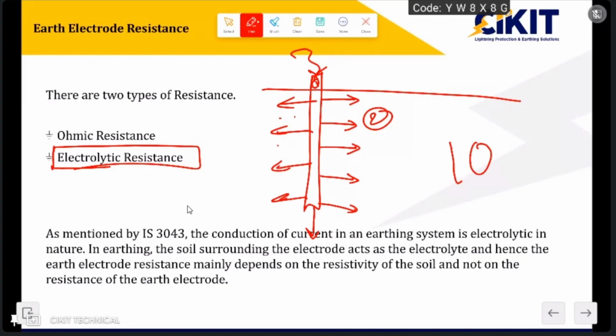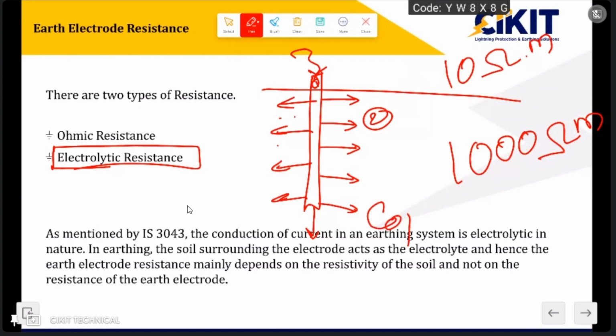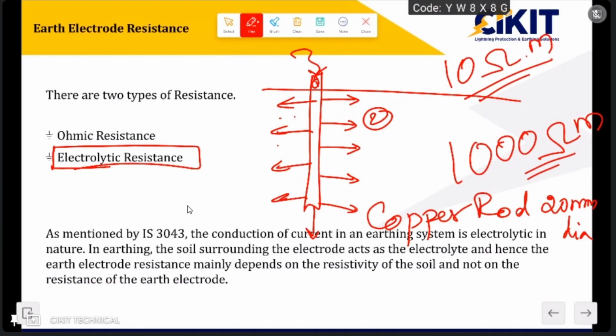If you take one site condition where the soil resistivity is 1000 ohm meter, and we take another soil of 10 ohm meter, and I install the same earth electrode, for example, a copper rod of 20 diameter, on these two conditions, 10 ohm meter and 1000 ohm meter, definitely the earth electrode resistance value will be different, because the earth electrode resistance value mainly depends upon the soil and it does not depend upon the material which we are using. So definitely, since there is a huge difference in the resistivity of soil, the earth electrode resistance value will be different.